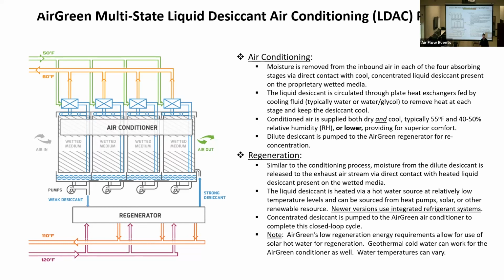We can turn individual stages on and off. We can change fan speeds, and all those things go to the performance. One of the things that we learned from operating a single system in the small hemp operation was that we probably should have had a separate chilled water coil, because we really weren't separating latent and sensible very well. Early in the grow, it's all sensible, and late in the grow, it's all latent. And so there are different criteria for managing those different stages.